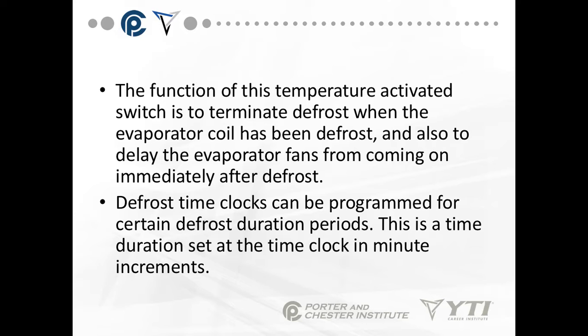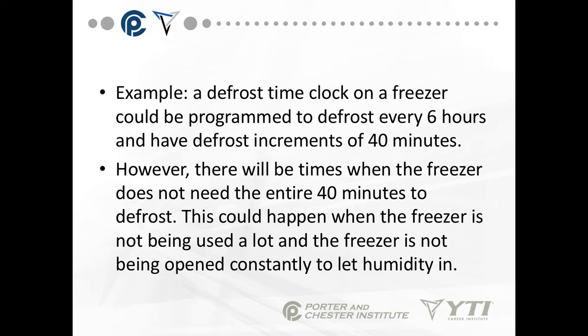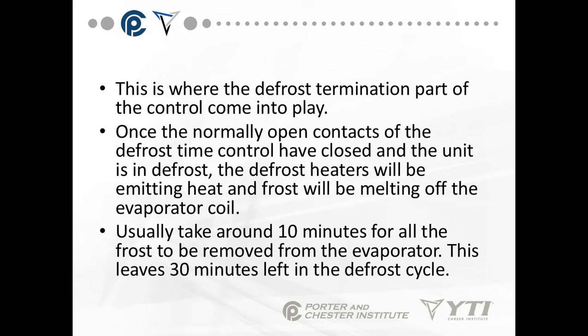Defrost time clocks can be programmed for certain defrost duration periods — a time duration set at the time clock in minute intervals. For example, a defrost time clock on a freezer can be programmed to defrost every 6 hours with defrost increments of 40 minutes. However, there are times when the freezer does not need the entire 40 minutes to defrost — such as overnight when the door is not being opened as frequently or when the freezer is not being used a lot. This is where the defrost termination part of the control comes into play.